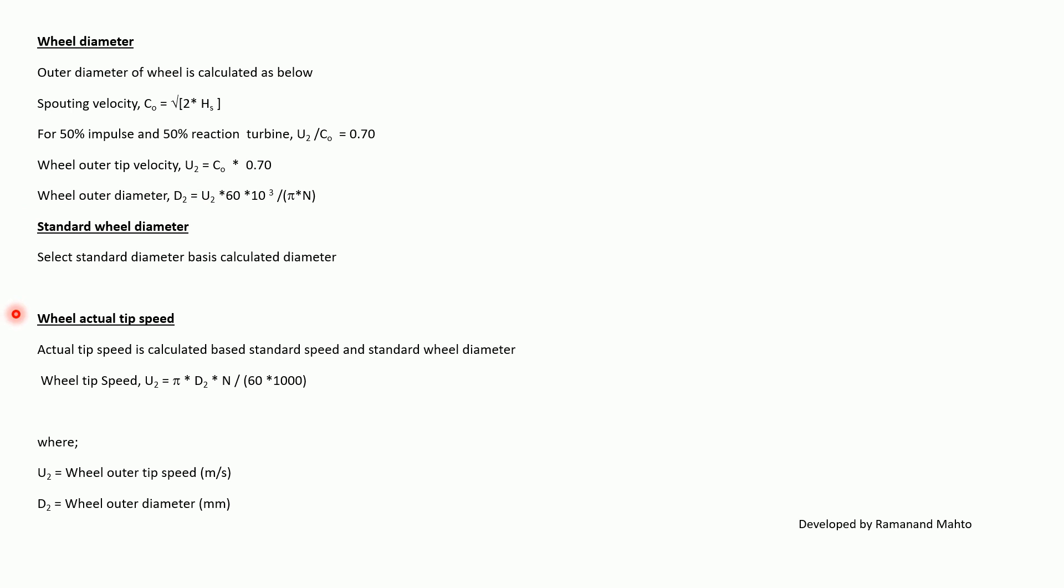Wheel actual tip velocity or tip speed: actual tip speed or velocity is calculated based on the standard speed and standard wheel diameter, which is expressed as U_2 is equal to pi times D_2 times N upon 60 times 1000, where U_2 is wheel outer tip velocity in meter per second and D_2 is wheel outer diameter in millimeter.